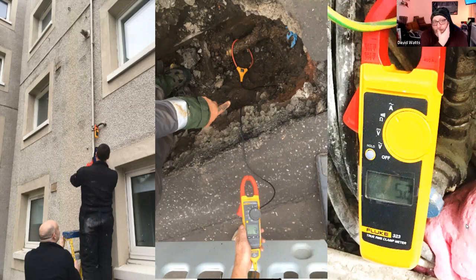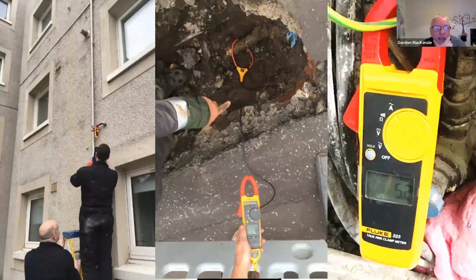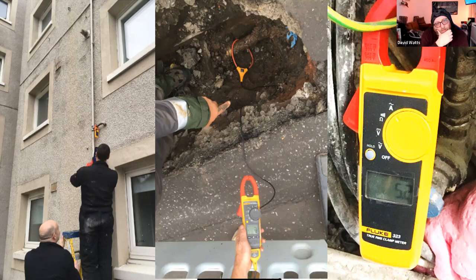Is this a common working practice now for the gas guys? That's very common, and where it requires mechanical protection - whether externally or rising internally in buildings - it remains, although hopefully sometimes it'll be PE when it goes back towards the main. But as it remains connected to the building, cast throughout the building, it allows current to flow between the flats.